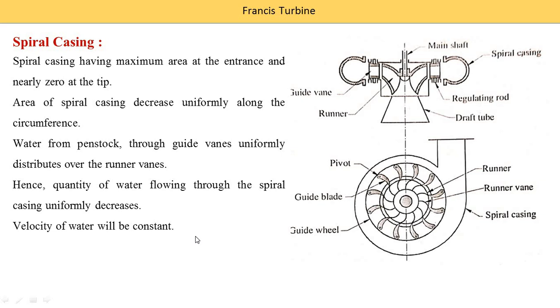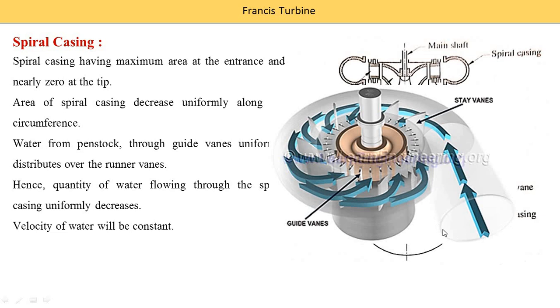If we think the area of the casing is reduced continuously, then velocity should increase. But in this case, velocity remains constant because quantity Q is not constant — it is continuously reduced as water is supplied to the different guide vanes. Quantity is reduced, area is also reduced, so velocity remains constant in spiral casing. Here the inlet of the casing shows water entering, area gradually reducing, supplying water to different guide vanes.